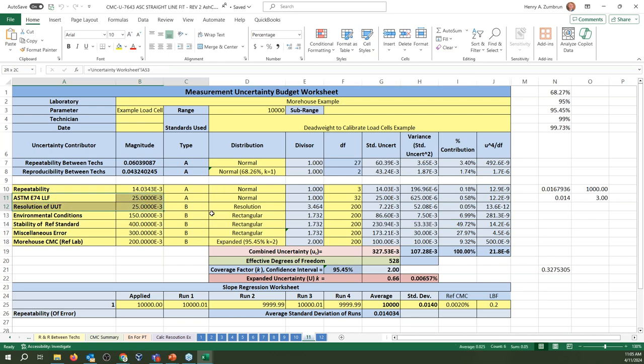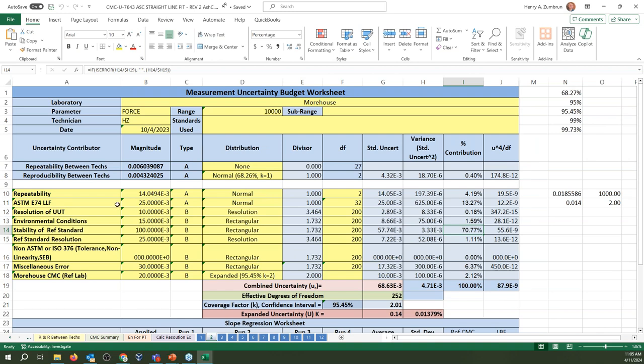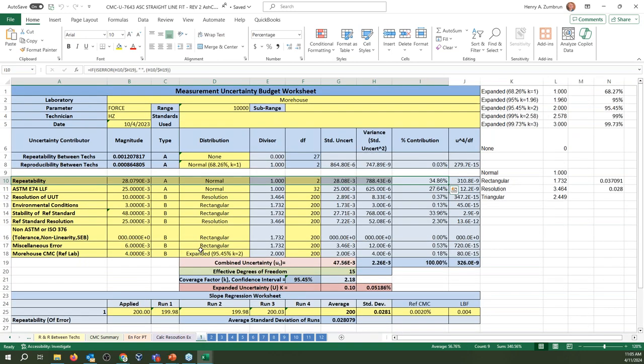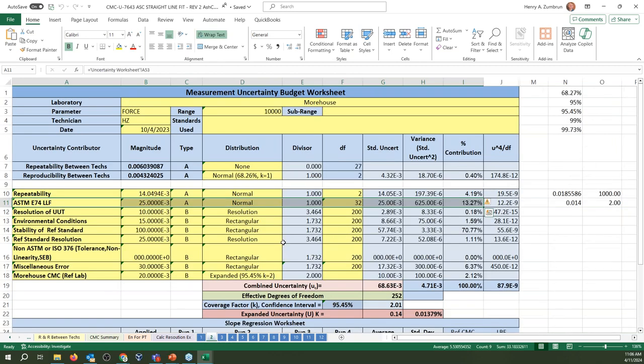Now this is at capacity. See the ASTM lower limit factor here? At capacity, it's 0.58%. If we go to the 10% point, 1,000 pounds, the ASTM lower limit factor is 13.27. If we go to our first point here, which is 200, the ASTM lower limit factor is 27, because that's a constant, it's not changing. Stability is still 33.96%. However, repeatability is starting to become dominant on those low force points. On a 2% point on a 10,000 pound load cell, in this example, we're at 0.05%. So when I say you're going to need to change standards, you might be able to do 10% to 100%, but going below 10% is going to be very, very difficult.